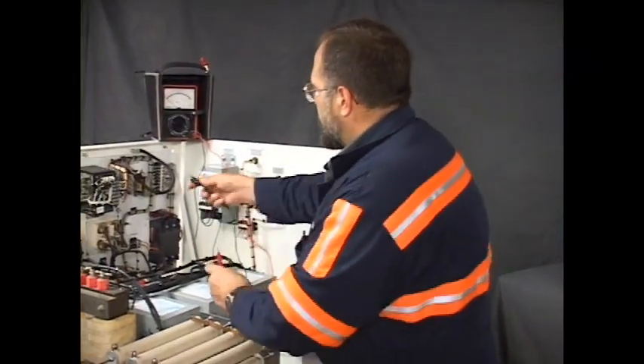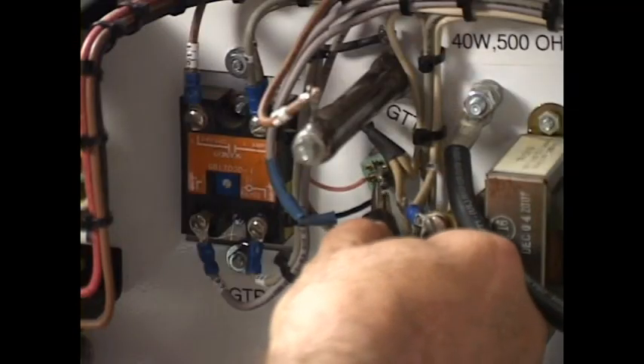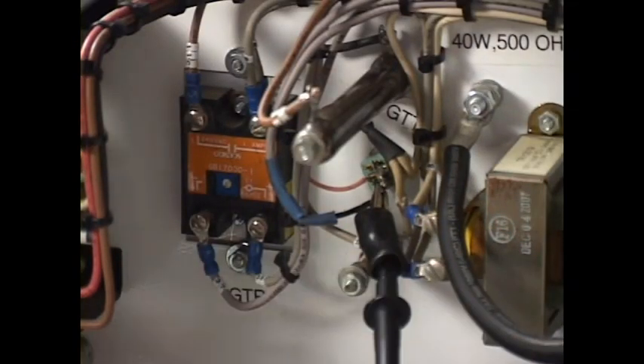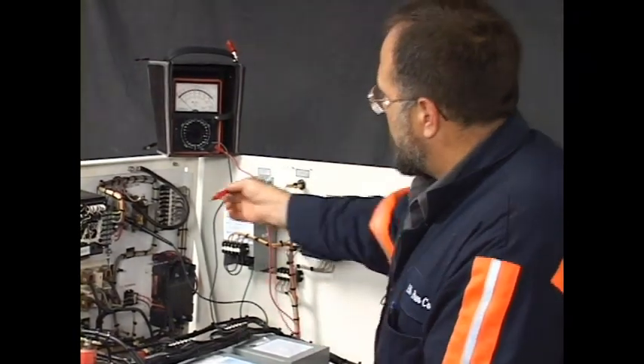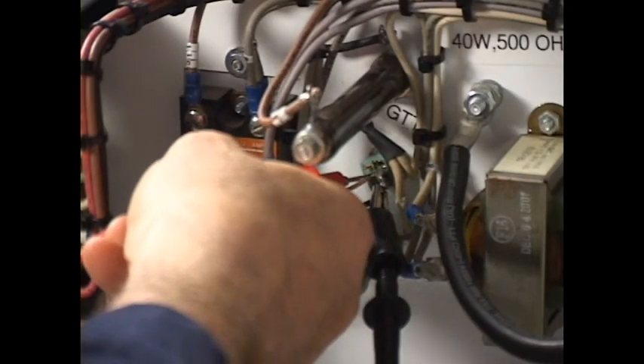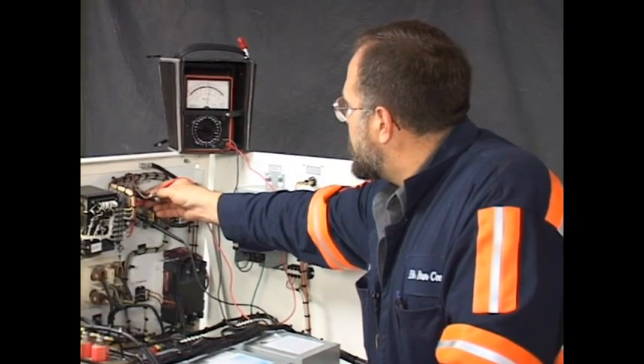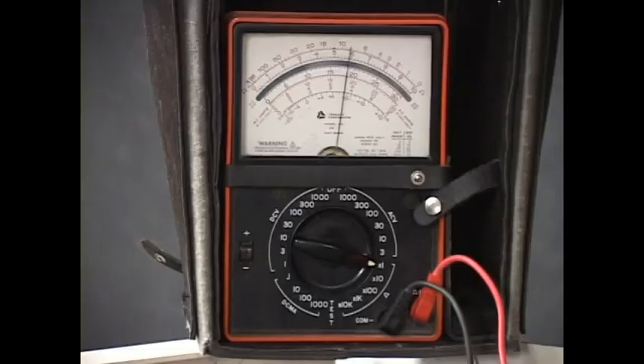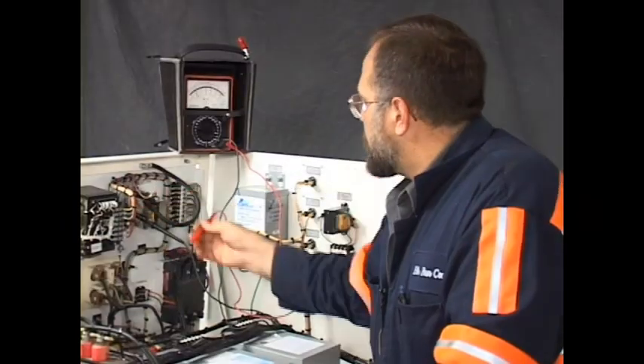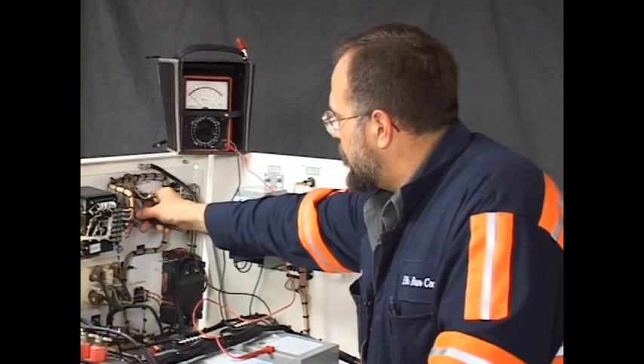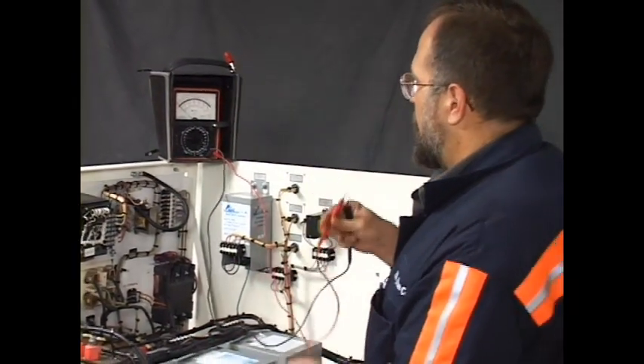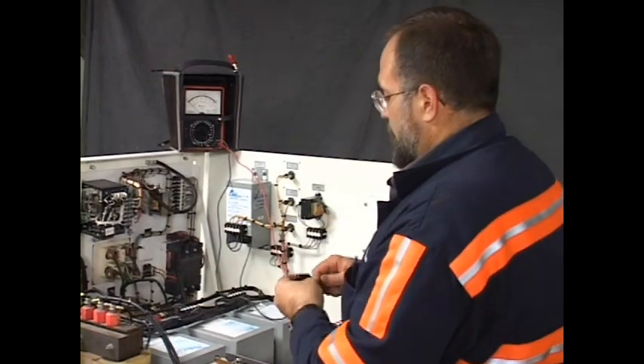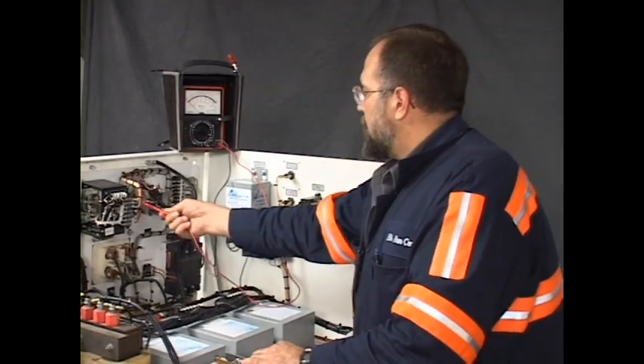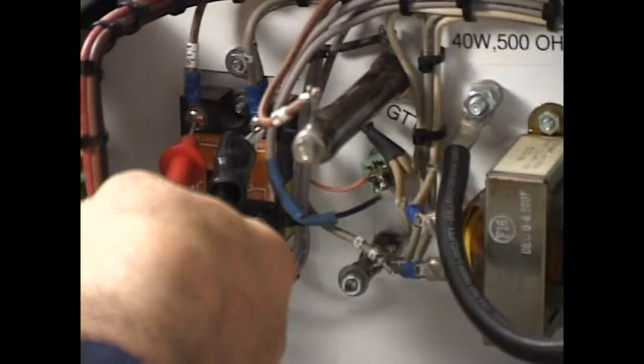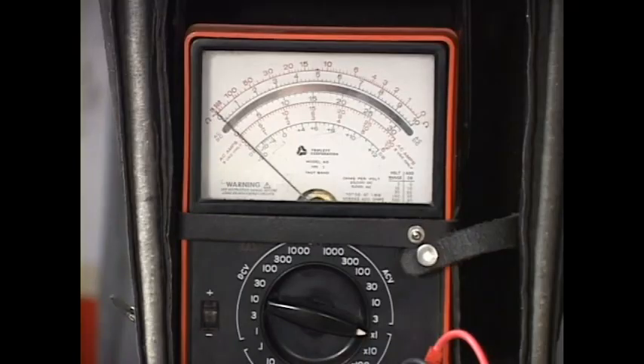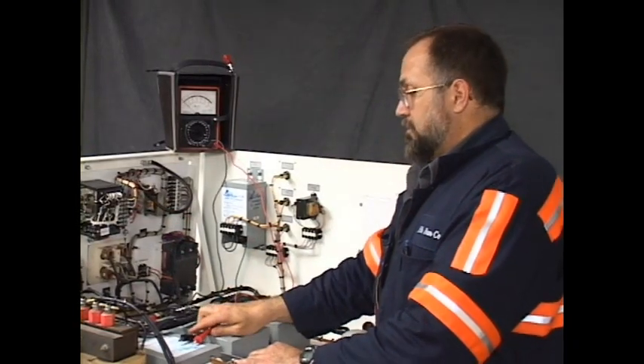I'm going to attach my black meter lead to one side of the switch with the alligator clip, and with the other lead I read, and as you can see, I'm reading approximately 9 ohms, which is as it should be. Now, the GTR should read open on its contacts, and I'm going to read from wire 11 to wire 8 on the 2 contacts on the GTR, and it reads open. That is as it should be.